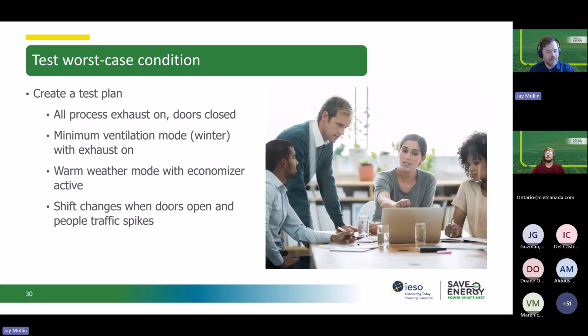Looking at minimum ventilation mode in winter, where you're bringing in only the minimum outdoor air that's needed, but you still have your exhaust on at full capacity. Warm weather, when economizers are active and bringing in more air, or when there's things like shift changes, when doors open and the people traffic spikes throughout the facility. And it's really important to consider these worst case conditions and test for those in the study, because the last thing you want to do is go through the study and assess the problems and make those changes based on typical operating conditions, but then still have problems when these kind of worst case scenarios arise.